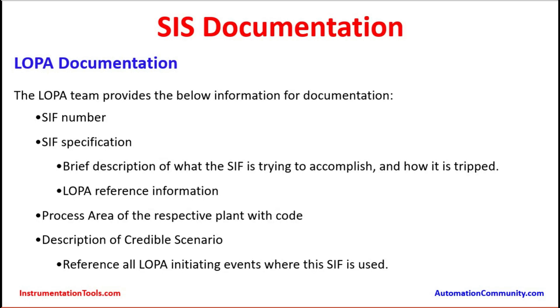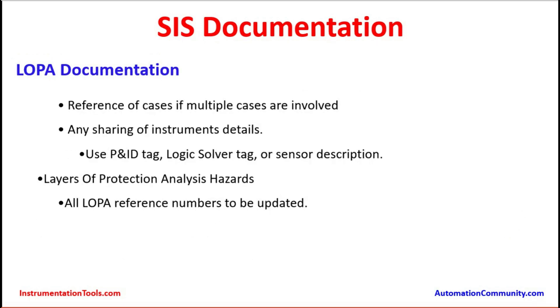LOPA has multiple scenarios, each with a different initiating event. Wherever a safety function is built based on a particular scenario, that reference number has to be included. Reference of cases if multiple cases are involved — for example, there could be a fuel gas high pressure scenario and a fuel gas low pressure scenario. In both conditions, the main inlet valve has to be closed as a safeguard to protect the boiler. These two LOPA files will be a part of two different case scenarios, which is what is meant by multiple cases.